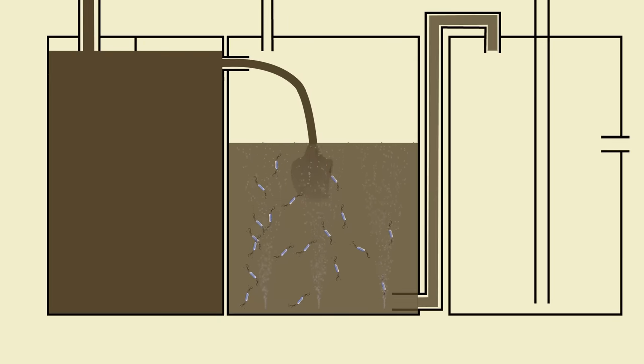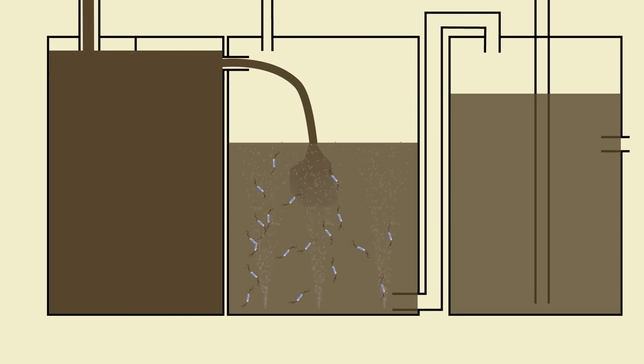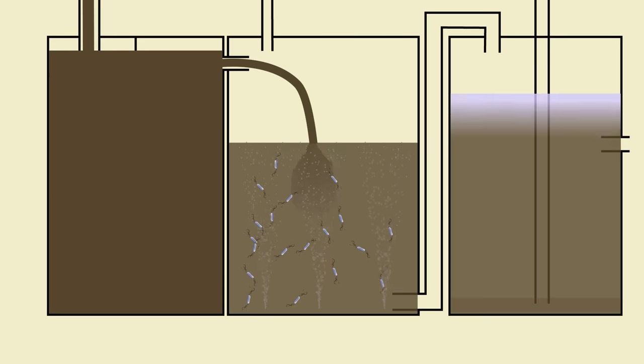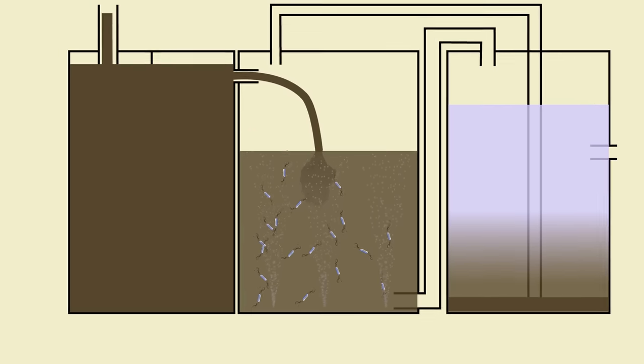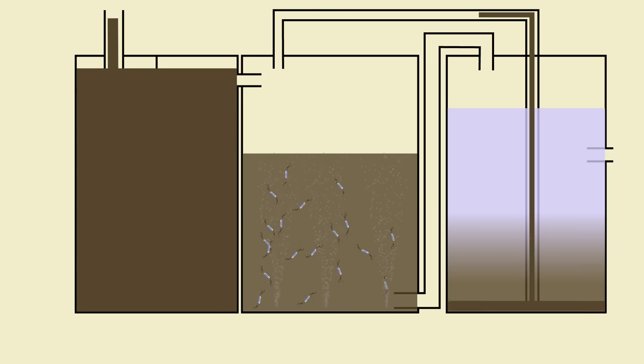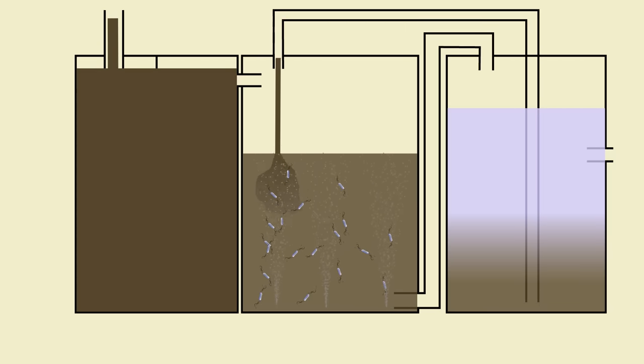It's a bit like a cocktail that you've left out for too long — you know where it separates out into layers. In our case, the dense heavy material sinks to the bottom and the water floats to the top. It's easy enough to deal with the dense stuff — you can actually just send it back to the beginning and keep cycling it through the bacteria until they've eaten through all they can. At some point it will become so dense that it gets caught in the filters, and then it can be removed and either sent for incineration or landed ashore.